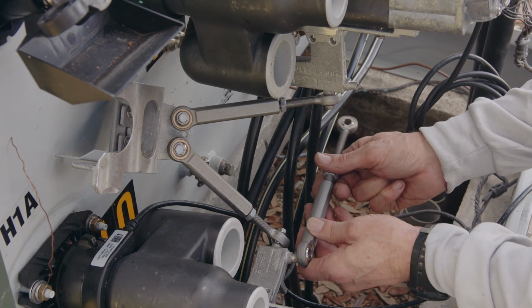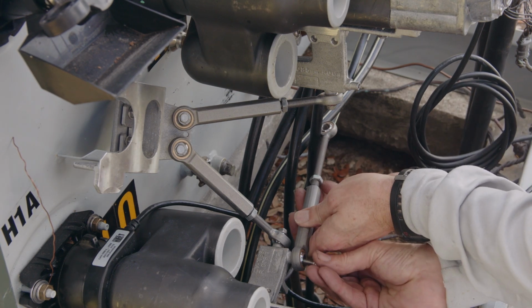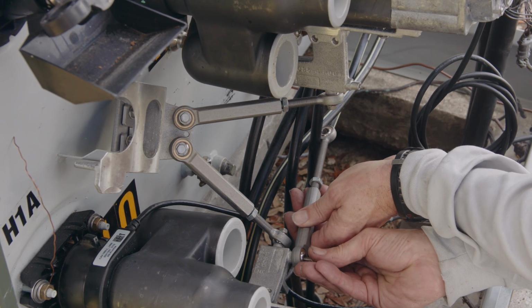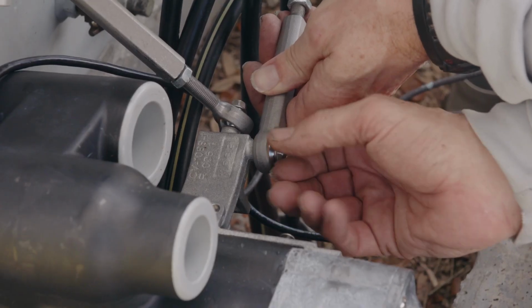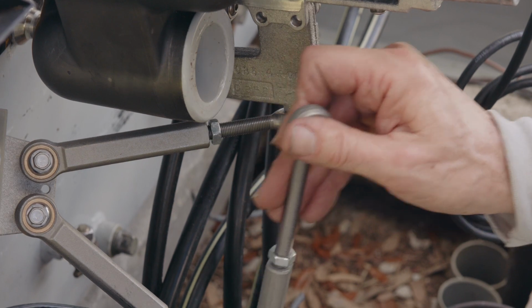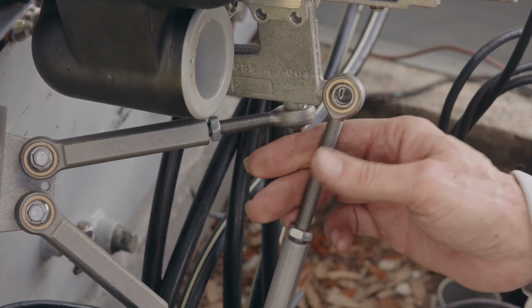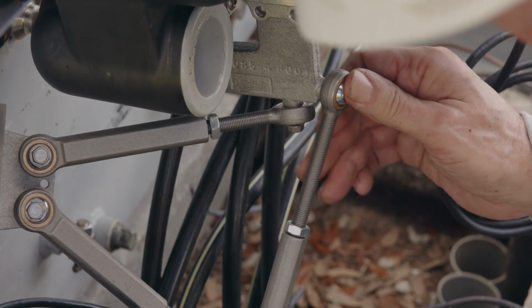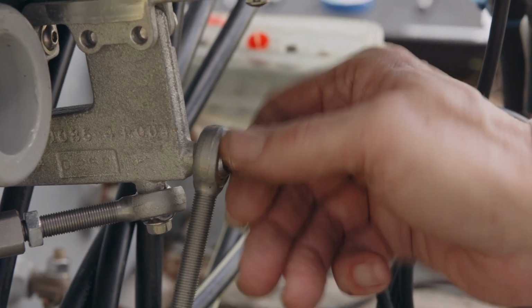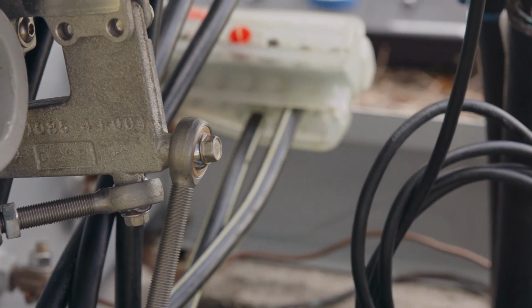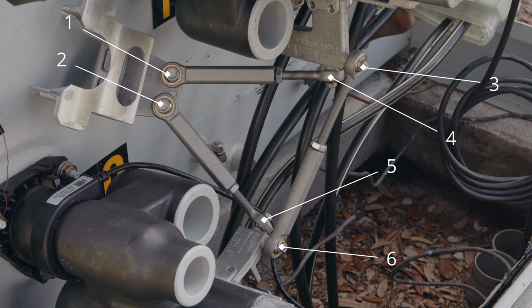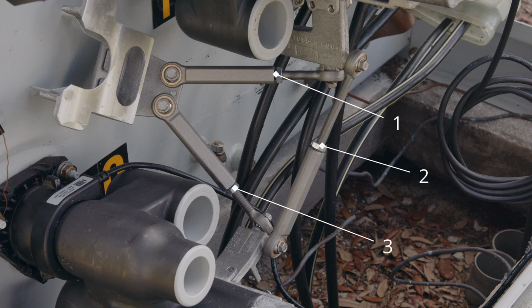To install the H1A to H1B cross brace link. Step 1. Install the adjustable cross brace link onto the H1B bushing well interrupter boss with a 1/4 inch by 20 flange head bolt finger tight. Step 2. Adjust the length of the cross brace link until the ball joint just fits onto the boss on the H1A bushing well adapter bracket. Step 3. Install a 1/4 inch by 20 flange head bolt finger tight. Step 4. Tighten the 6 1/4 inch by 20 flange head bolts, 2 on each end of the adjustable links, and cross brace link to a torque of 75 inch-pounds. Step 5. Tighten the 3 jam nuts, 1 on each of the 2 adjustable links and 1 on the cross brace link.